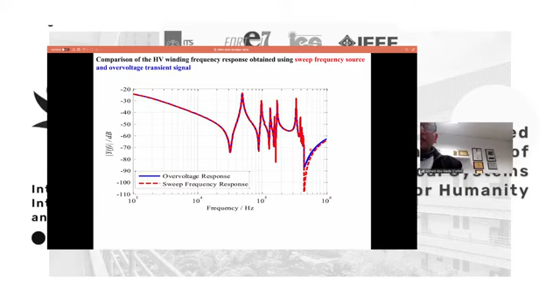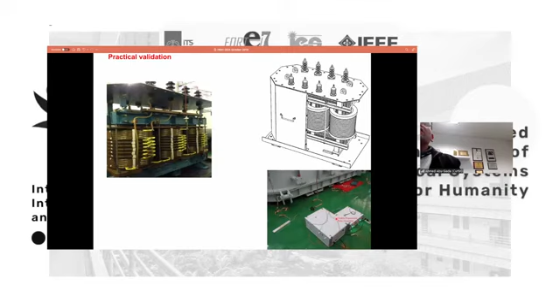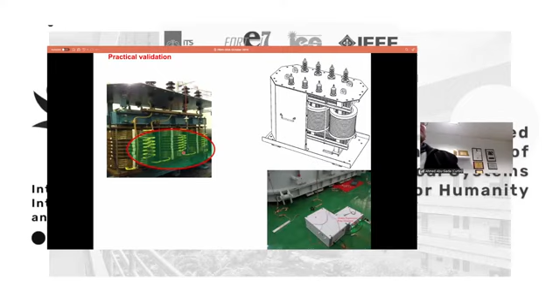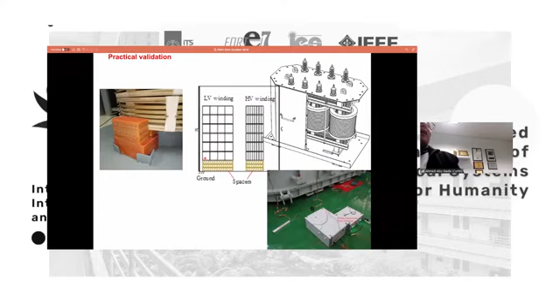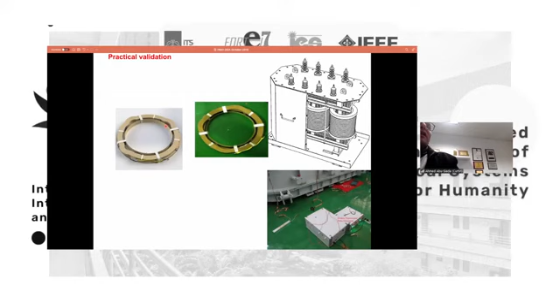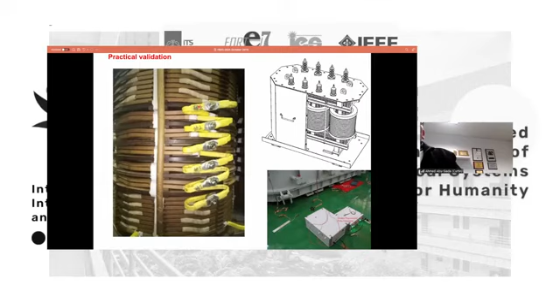So this technique can be very practical for operating transformers. We did a lot of work on this to find out if we can detect all types of faults. We created a short circuit winding, and also what's called axial displacement—I'll explain later what axial displacement is, when the winding moves downward. We also created buckling of one degree or more. For the short circuit, we simply shorted some turns. Through this technique we could detect the fault.